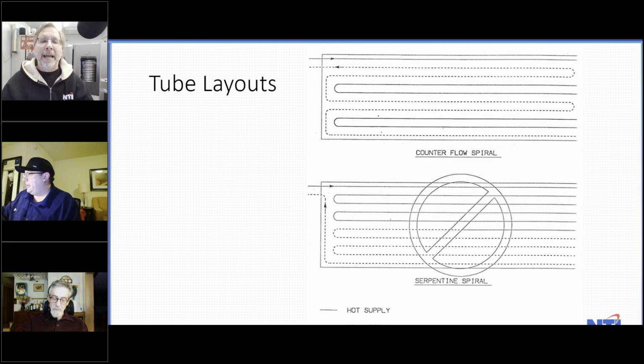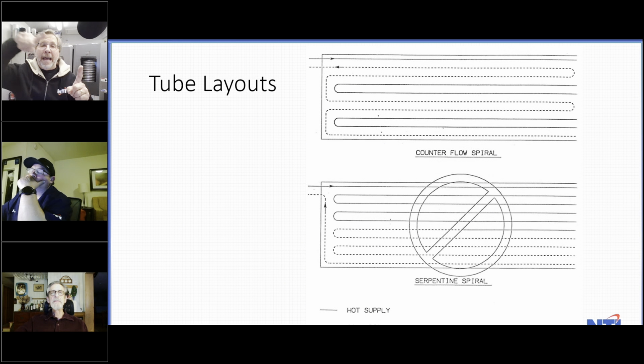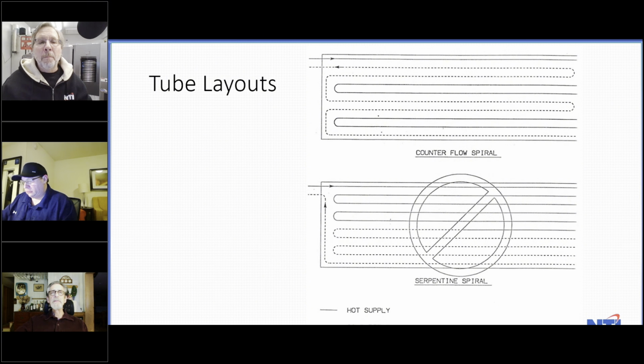Here we go, tubing layouts. Never run back and forth like you do for radiant heat as shown on the bottom. Always use a reverse return like shown on the top, or use a counterflow spiral where you spiral out around the outside, get to the center, and then come back in between all the loops on the outside. Please do either so you get even snow melt, or you're going to get streaking and people won't be happy.